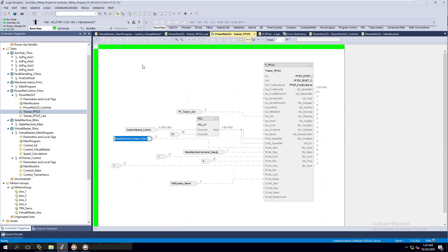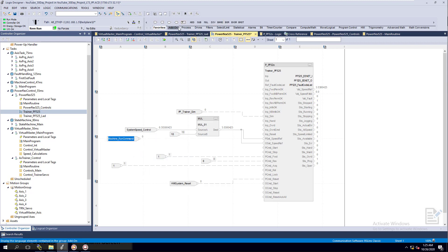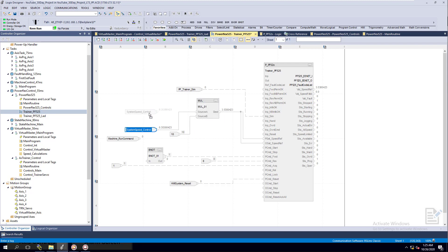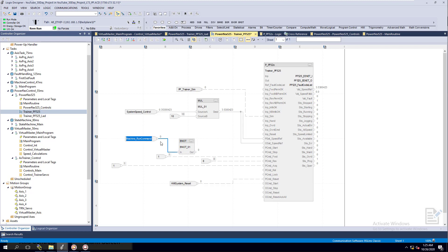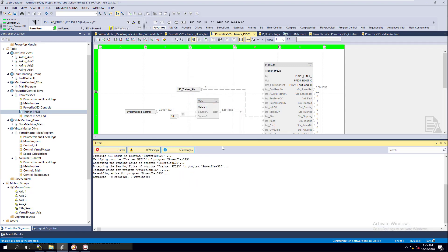I'll show you how to program this quickly. We delete the current pins and add them back in. I'll add a NOT instruction — why? Because if the machine run command is on (high), it will run; and if it's NOT on, that bit being not high will tell it to stop. So we run forward, and the machine run bit drives the start, while the NOT of machine run drives the stop. Let's test that so you can see it actually working.